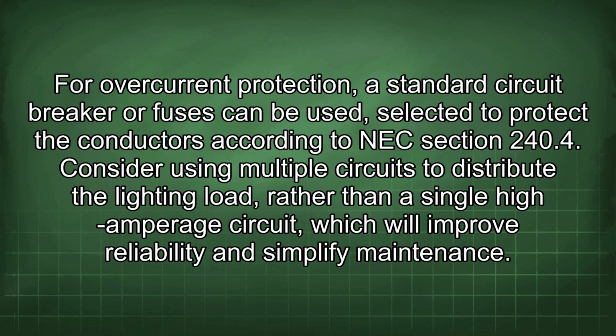For overcurrent protection, a standard circuit breaker or fuses can be used, selected to protect the conductors according to NEC Section 240.4. Consider using multiple circuits to distribute the lighting load, rather than a single high amperage circuit, which will improve reliability and simplify maintenance.